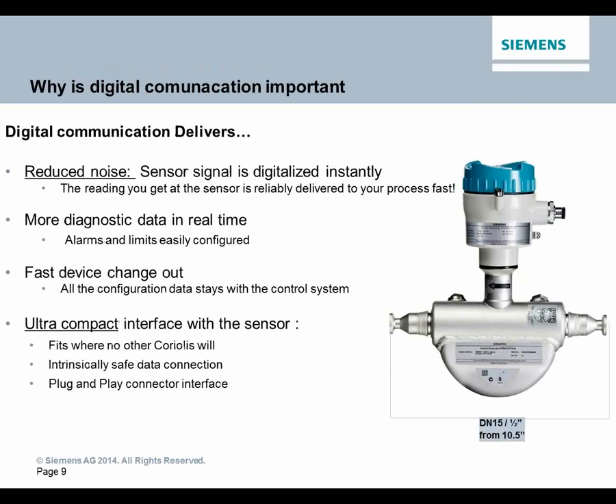Yes. Pipe warp. Does piping torque affect the accuracy? Fantastic question. You're falling right into my trap. Very good for asking that one. Okay, so in the installation of the meter, I can see we're going to run long now, so I'm warning you now. In the installation of a Coriolis meter, the very simplest answer to your question is absolutely. Yes, definitely.